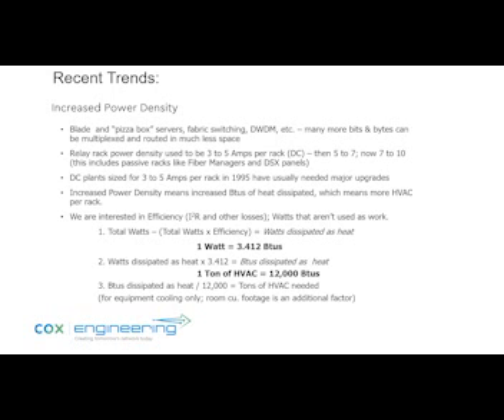And assign a certain kW per rack based on what you have, what you know, and recent trends, and maybe a little bit of headroom, and then do the conversions, and then you would have the cooling that would be required for each of the rooms.